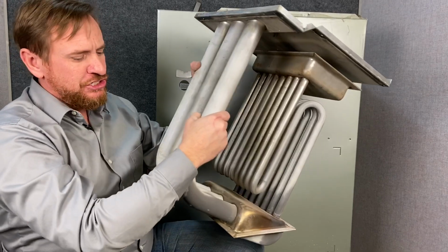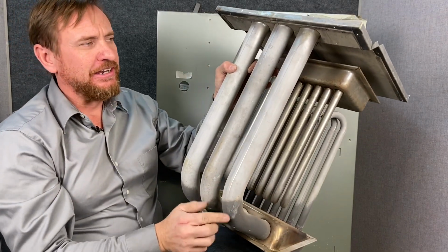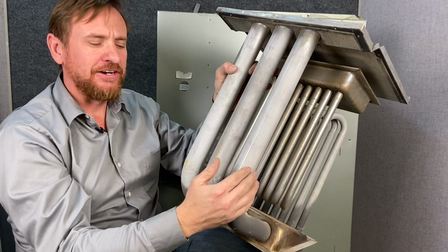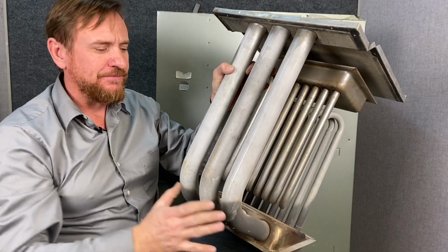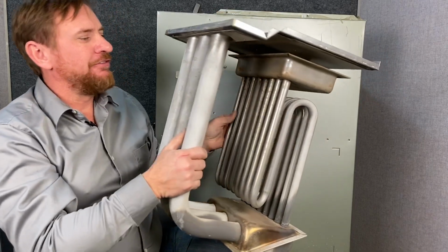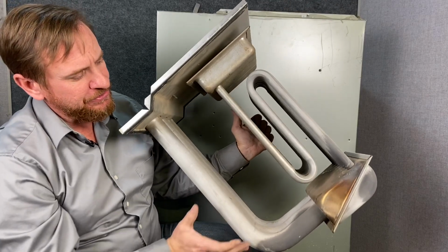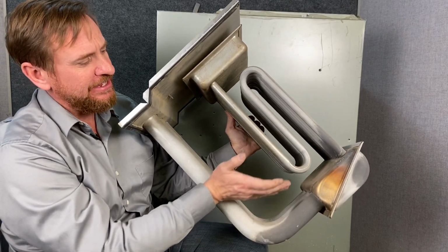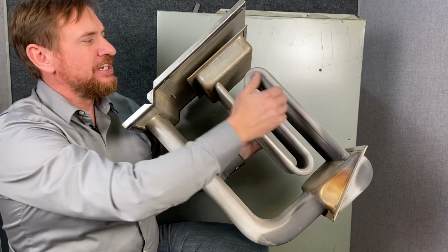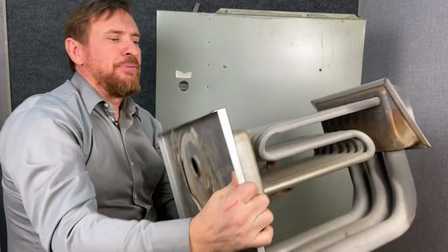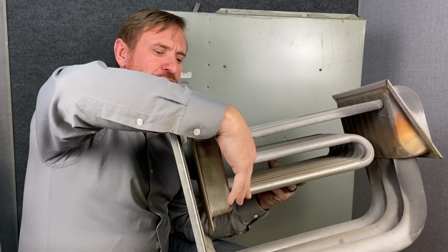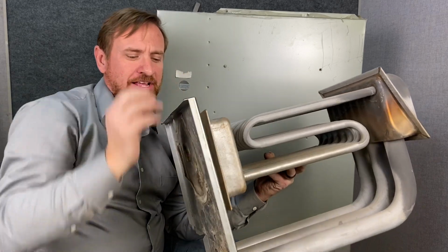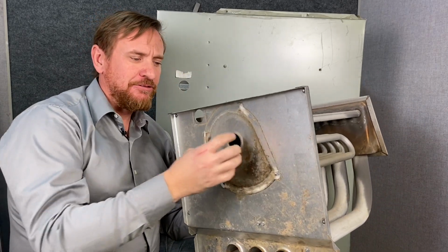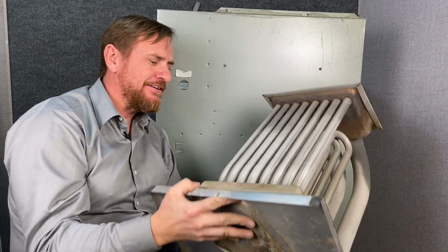And also we want to check the back of the burners right here. If somebody sets this up to overfire, it'll actually burn out right here. So the blower is going upflow. It's pushing the air up through the heat exchanger this way, the primary first, then it goes across this part of the heat exchanger. And then we pull all the gases together through these tubes to this little collection box, and this is where the inducer fan is, that's pulling that draft of the whole thing. So this is our heat exchanger.